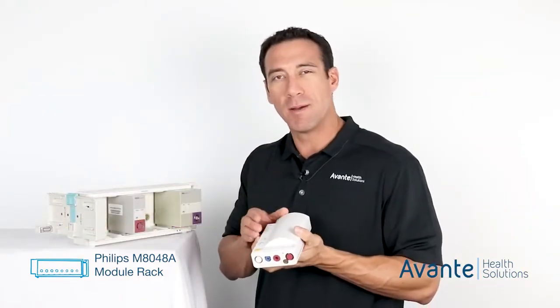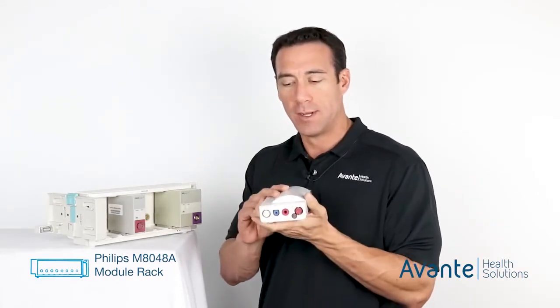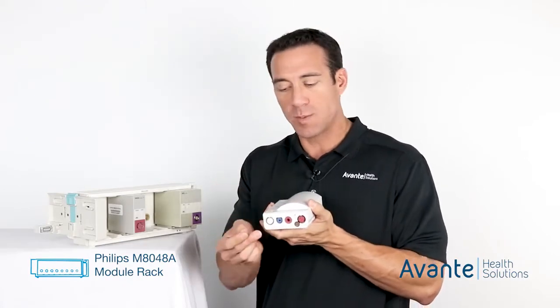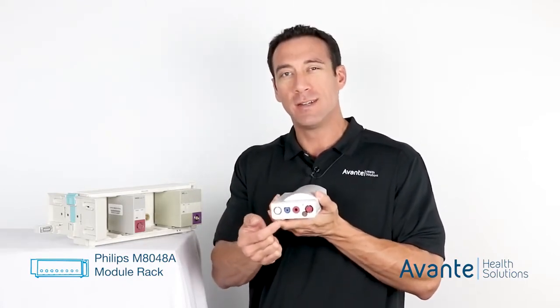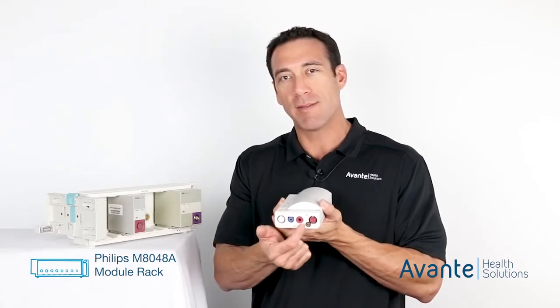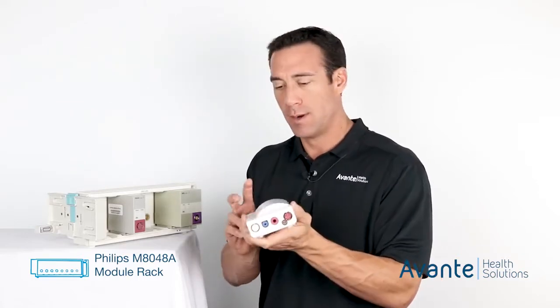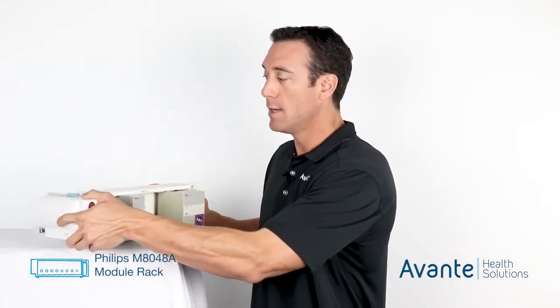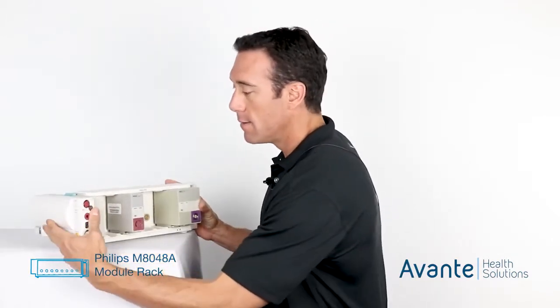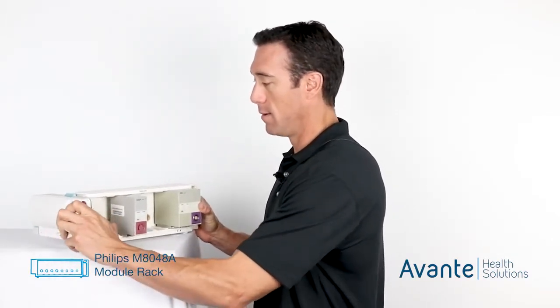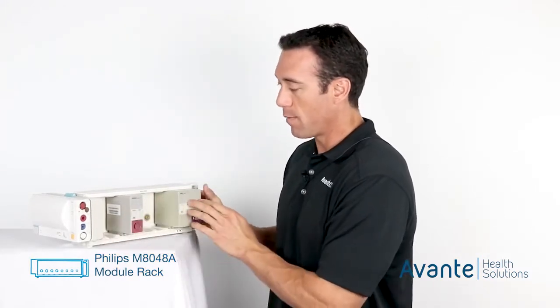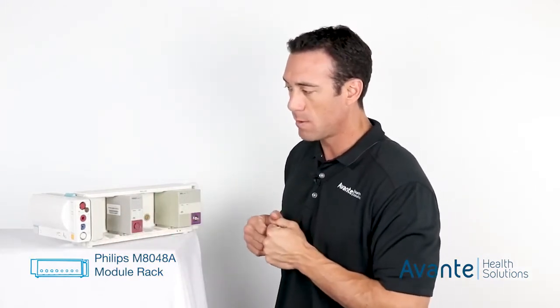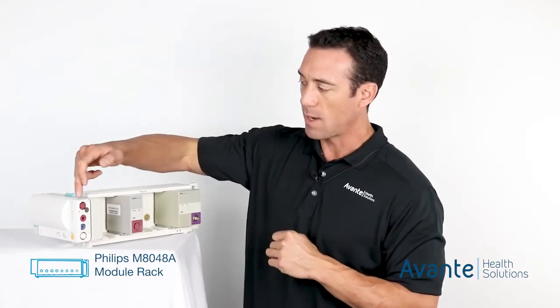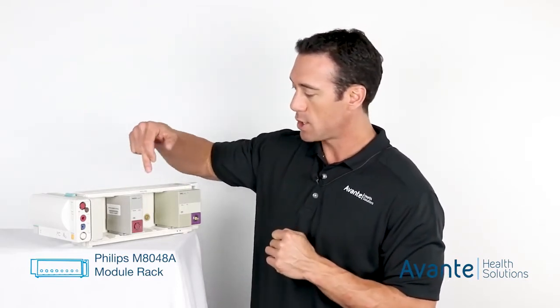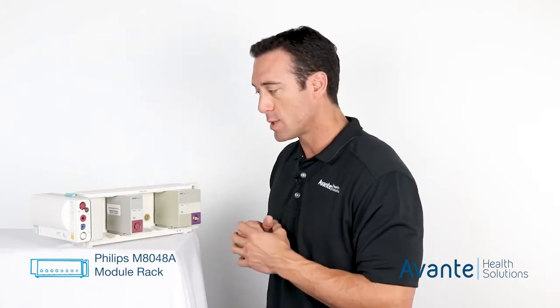On the Philips M8048 module rack, we can also plug in the multi-measurement server. We've gone over multi-measurement servers, but you'll have SpO2, ECG, NIBP, and the option again of pressure and temperature. This slides into the side rack and clips right in, giving numerous measurements available to the clinician — everything on the multi-measurement server, plus the additions of the singular modules.